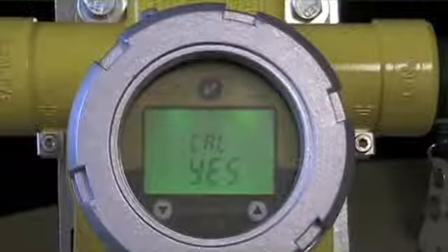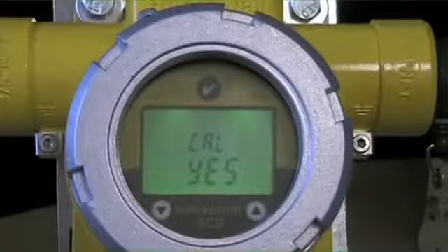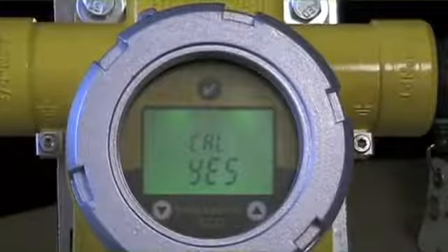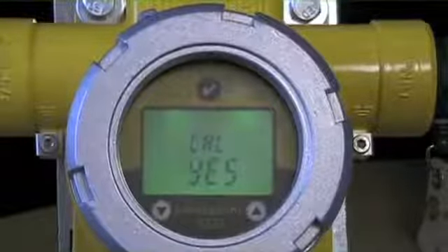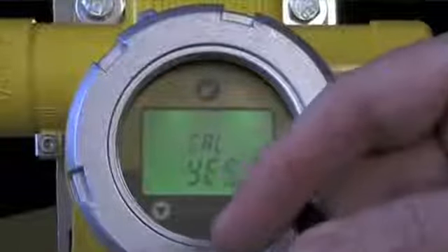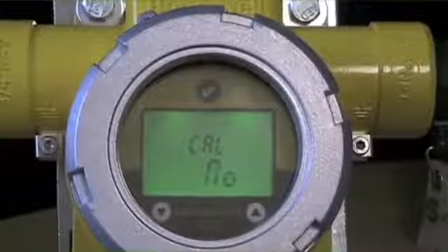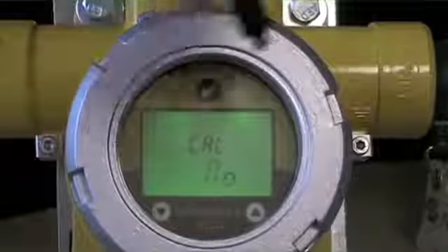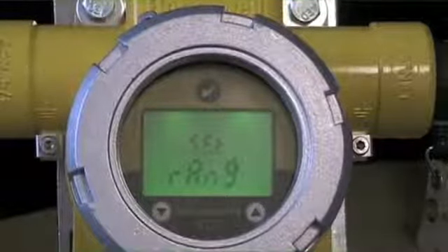The next step, because we've changed sensor range, is the instrument's going to ask you whether or not you want to be recalibrated. Typically, you want to calibrate a sensor in the middle of its full-scale range. In this case, we've made a pretty substantial change to it. It's asking us if we want to recalibrate. So that's an option, and it's encouraged if you're making substantial changes. In this case, we're not going to do that. I'm going to simply scroll to No, enter that function, and I go back into the menu.